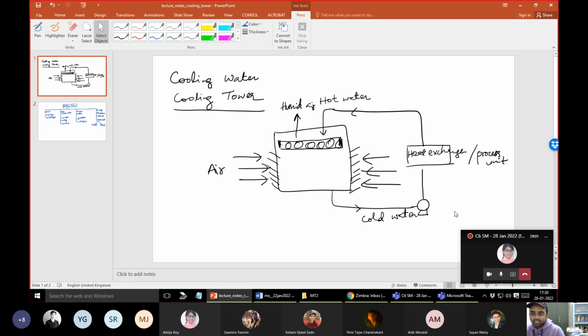So mostly towards the exit there is a counter current arrangement of air and water, but towards the exit of the water the air comes in sideways. So a part of the unit has this sideways movement of the air through the chamber, and this is what we call cross flow. So part of the unit operates under cross action, so the water and the air are not completely vertically opposite to each other.